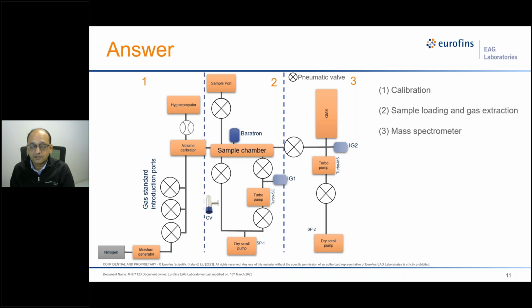Is that it has a special arrangement of valves where we can introduce a known amount of gas to the sample chamber, which is in section 2 here. So the volume calibrator has different volumes on it, like 10 cc, 1 cc, 0.1 cc, and 0.01 cc. So I can introduce the standard volume of gas into the sample chamber using the volume calibrator.